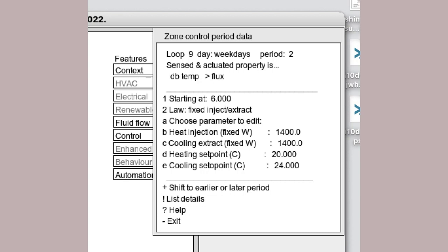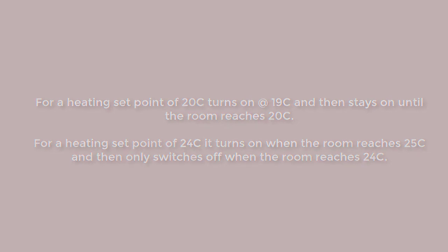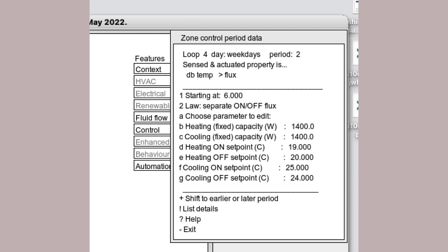Also, that control assumes that the thermostat will switch at the set point, whether the room temperature is rising or falling, and that it will not be overly influenced by its own hot surfaces, which might be rather optimistic. Let's say we monitored such a device and mapped out its actual response to changing room conditions. Given these, we then have an option for a much more specific control law to discover how room conditions might differ from that initial optimistic assumption.